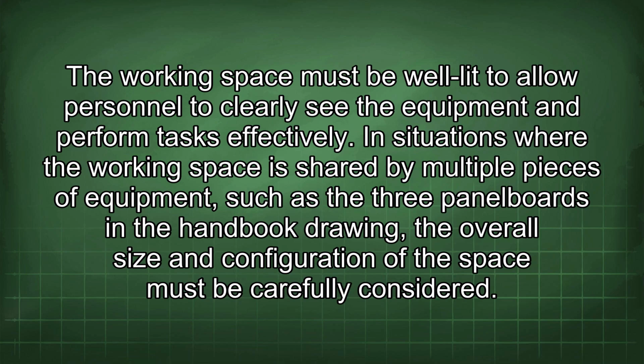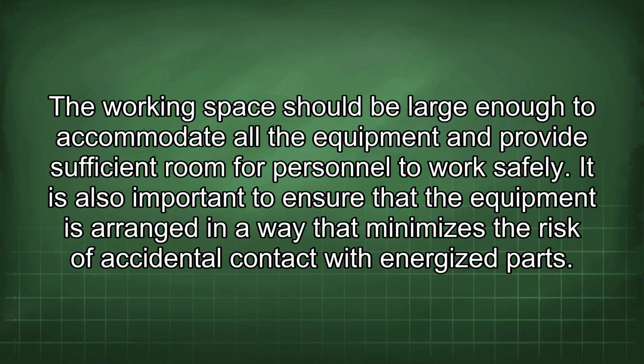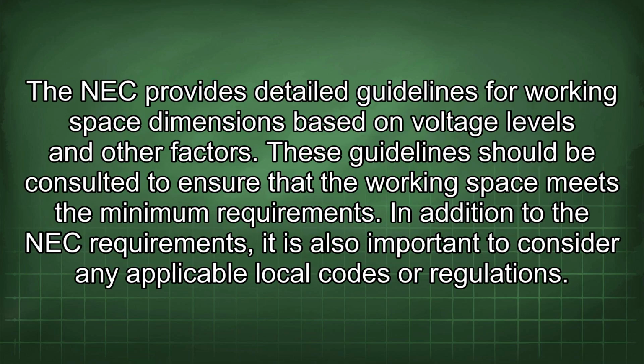In situations where the working space is shared by multiple pieces of equipment, such as the 3 panel boards in the handbook drawing, the overall size and configuration of the space must be carefully considered. The working space should be large enough to accommodate all of the equipment and provide sufficient room for personnel to work safely. It is also important to ensure that the equipment is arranged in a way that minimizes the risk of accidental contact with energized parts. The NEC provides detailed guidelines for working space dimensions based on voltage levels and other factors. These guidelines should be consulted to ensure that the working space meets the minimum requirements.